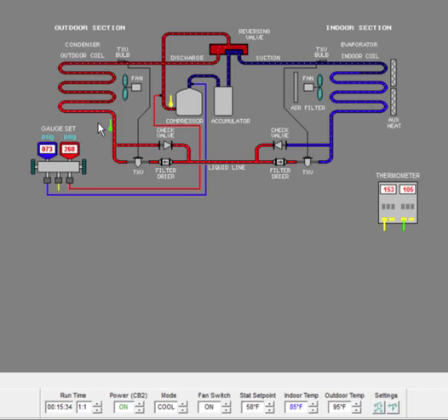So what we normally do is we take our high side gauge, convert it to a temperature. In this case, it's real easy. I just have to click on it. So I know my condensing temperature, which is my high side gauge converted to a temperature, is 120 degrees. Let's ignore the low side of the system for now. My outdoor temperature is 95 degrees. So we subtract the two numbers, 95 degrees from 120. I'll let you do that on your own for a real quick sec.